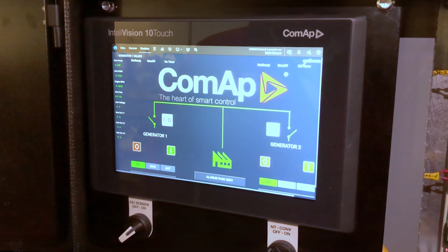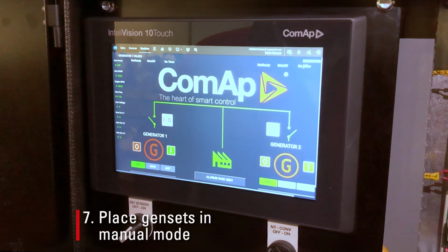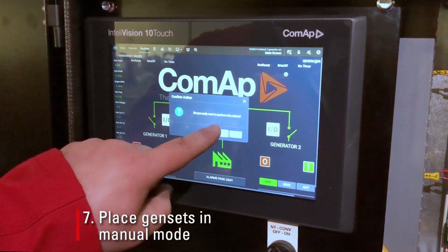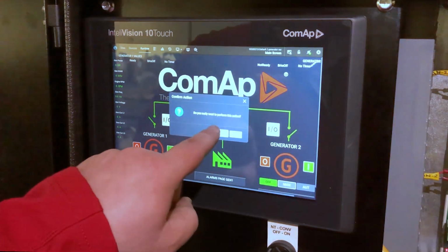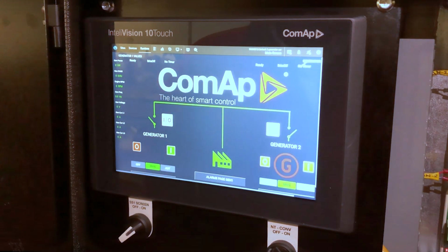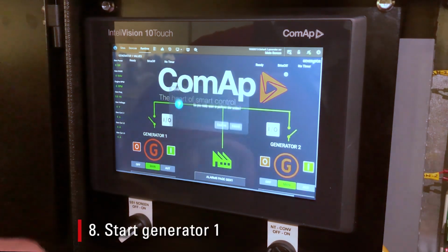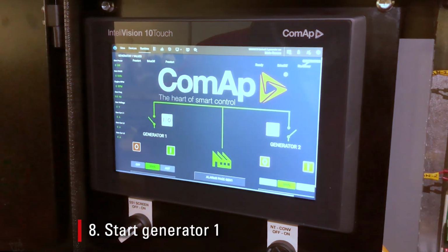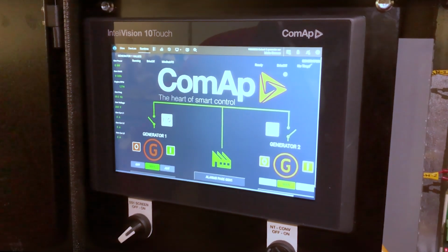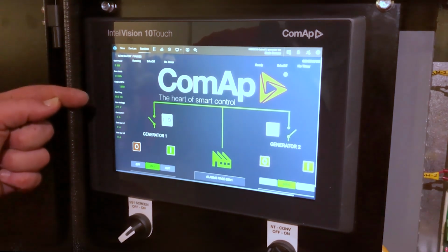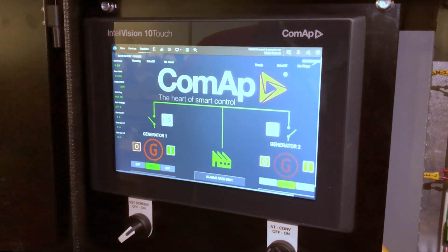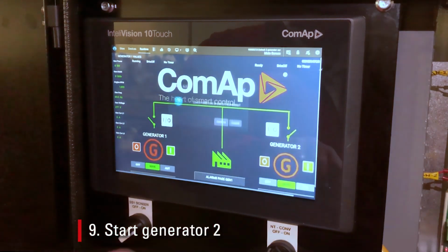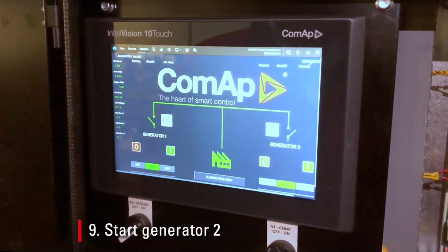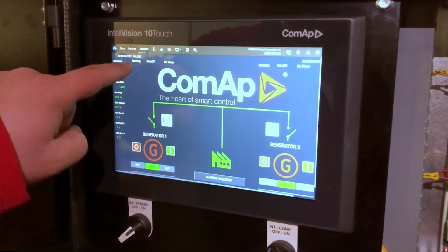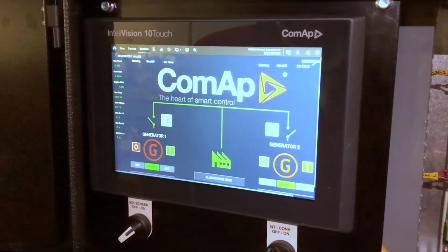When you are ready to manually operate the twin packs, begin by placing each genset in manual mode. Please note, by placing the gensets in auto mode, this operation would be managed automatically after an auto start signal is given. Having set your controller mode in manual, begin by starting generator 1 first. To do this, press the green start button. On the left side of the screen, you can see your rated speed, frequency, and voltage. Then we will start generator 2. At the top of the screen, you'll see indications of both generators running, and we can see both breakers are open.